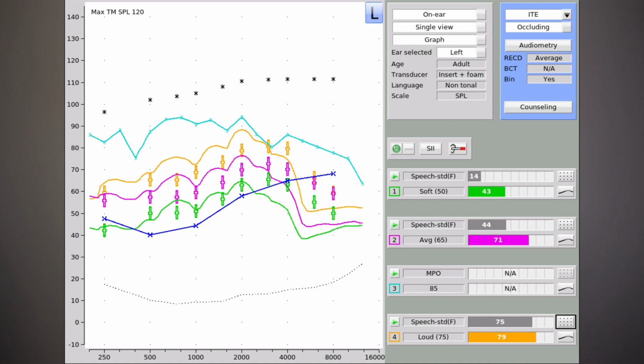And then if you had the hearing aids sent to you and they were this loud, you probably wouldn't like wearing them in your home because you hear all of these soft sounds when in reality they don't need to be set that loud. So just from the experience of me sending one hearing test and the company Audicus sending the hearing aids programmed to that hearing test, overall the thresholds were 5 to 10 decibels louder than they were supposed to be, between 500 and 2000 hertz. Between 3000 and 8000 hertz, the hearing aids were underfit, meaning that they were not providing enough sound. So for the bass tones, these hearing aids were sent to me, the bass was turned up too loud and the treble was too soft.